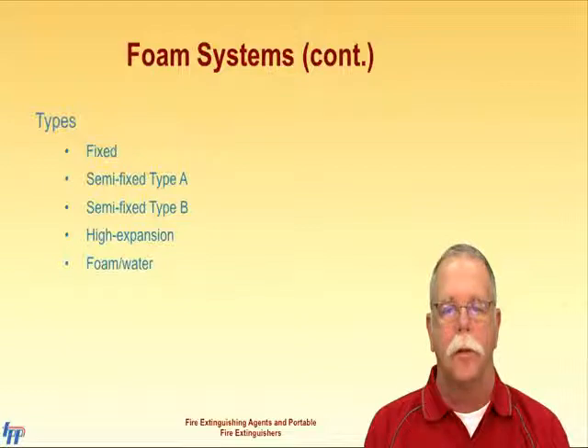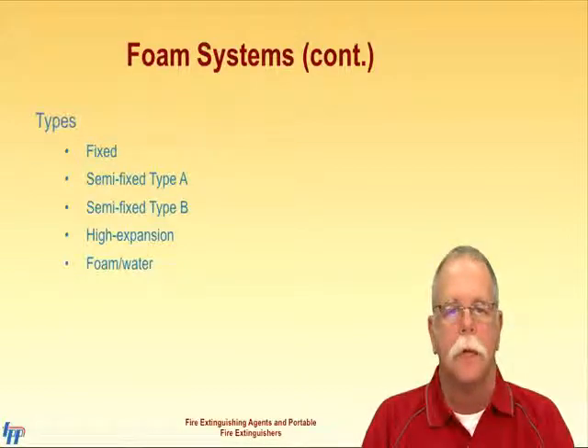A semi-fixed Type A system has the piping in place but not connected to a permanent source of foam. This may be a tank farm where one foam truck can connect to the appropriate system to deliver foam where it is needed. A semi-fixed Type B system has piping with a foam supply connected to it and with hydrants that allow the connection of hoses to the system. It is similar to a fixed foam system, except that a fixed foam system applies the foam to the hazard, while a semi-fixed Type B system makes foam available.